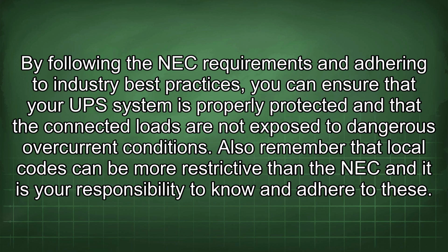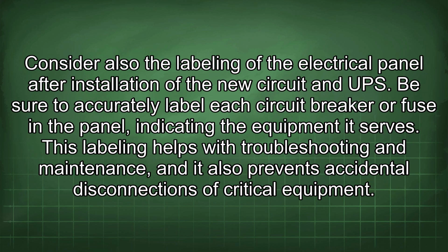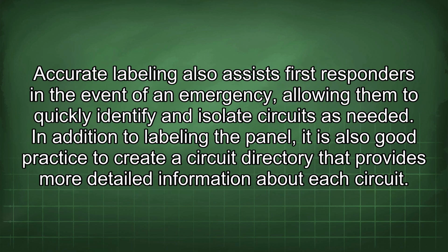Also remember that local codes can be more restrictive than the NEC, and it is your responsibility to know and adhere to these. Consider also the labeling of the electrical panel after installation of the new circuits and UPS. Be sure to accurately label each circuit breaker or fuse in the panel, indicating the equipment it serves. This labeling helps with troubleshooting and maintenance, and it also prevents accidental disconnections of critical equipment. Accurate labeling also assists first responders in the event of an emergency, allowing them to quickly identify and isolate circuits as needed.